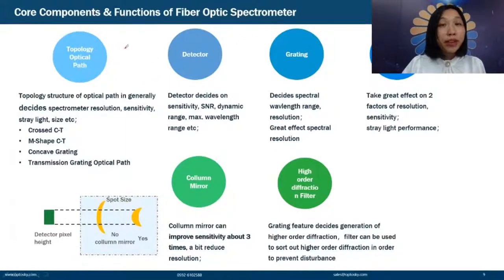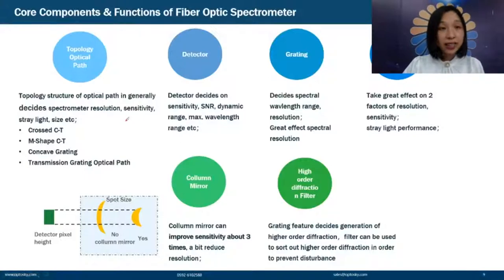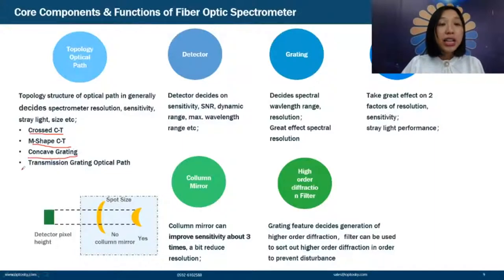For a fiber-optic spectrometer, the first consideration is the topological optical structure, which generally decides the spectrometer's resolution, sensitivity, stray light, and size. We have four types: the cross-CT optical path, M-shaped CT optical path, concave grating optical path, and transmission grating optical path.